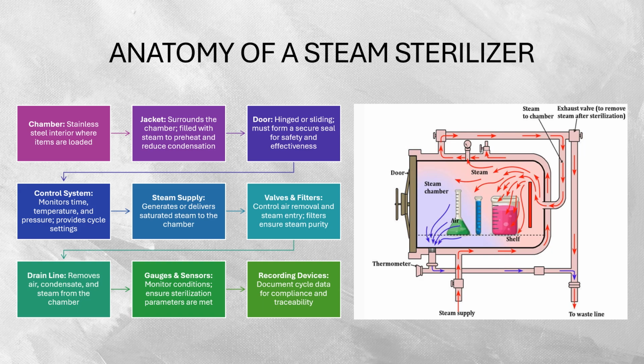A clean, reliable steam supply is vital for effective sterilization. The valves and filters help maintain air removal and steam quality. The drain line, which is at the bottom of the autoclave, is usually towards the door. So if you look into the chamber on the floor, you'll see kind of like a little top. That comes out. That's your drain line. The drain line removes unwanted materials, while gauges, sensors, and recording devices ensure that sterilization parameters are properly maintained and documented. We have to maintain and document everything that we do, especially in our sterilization phases.